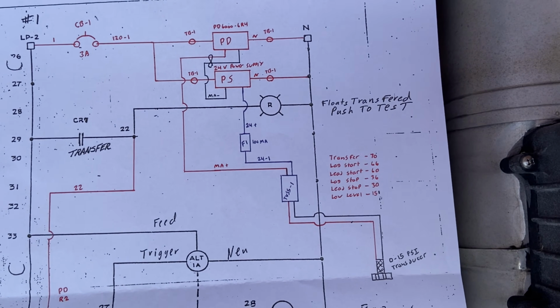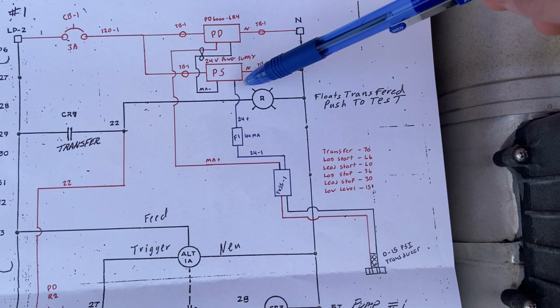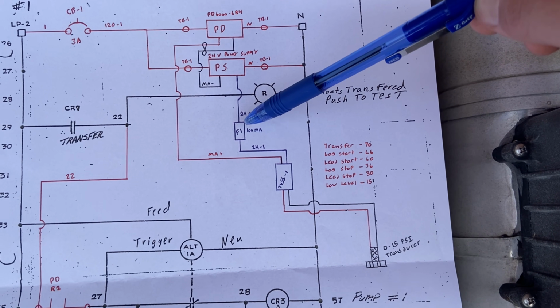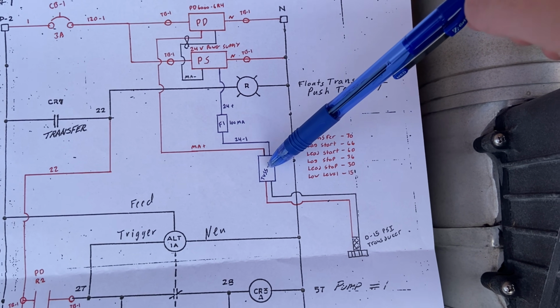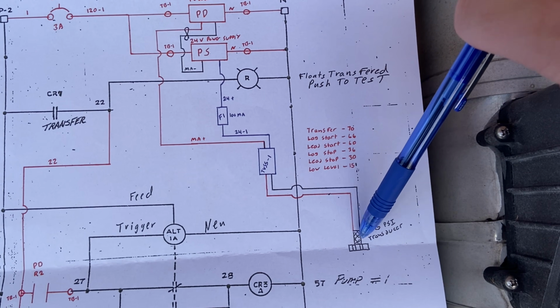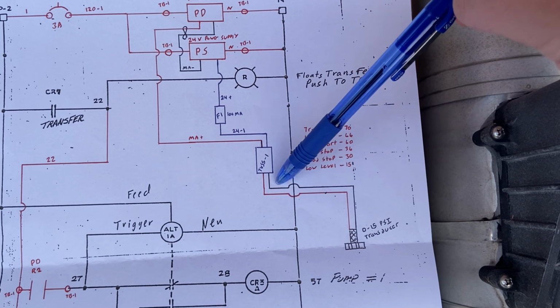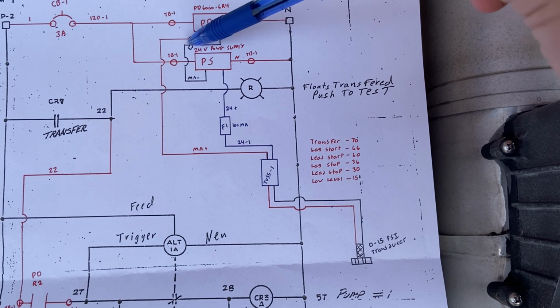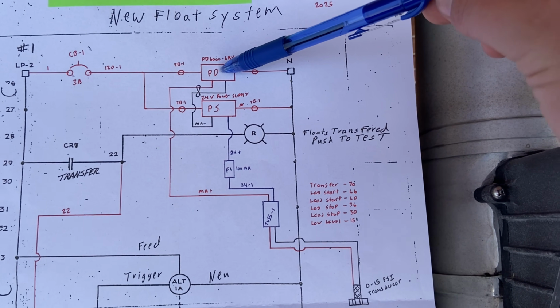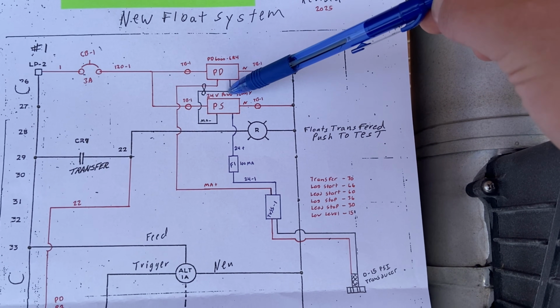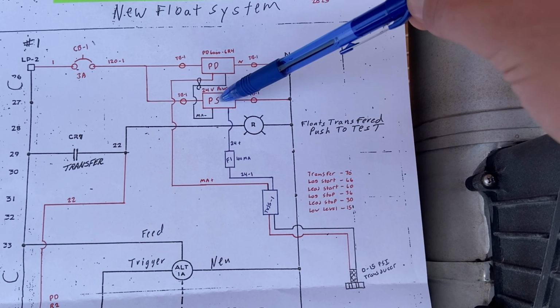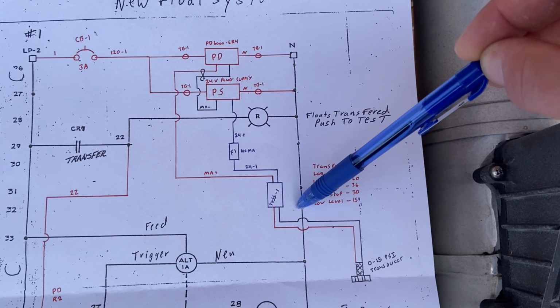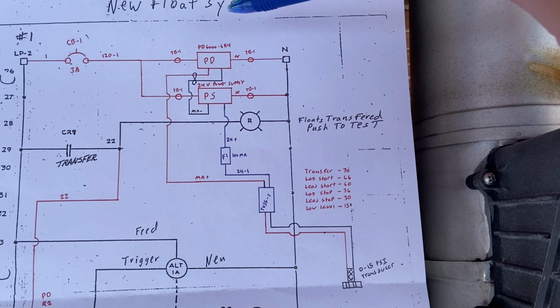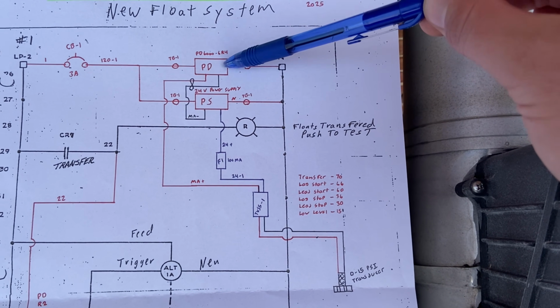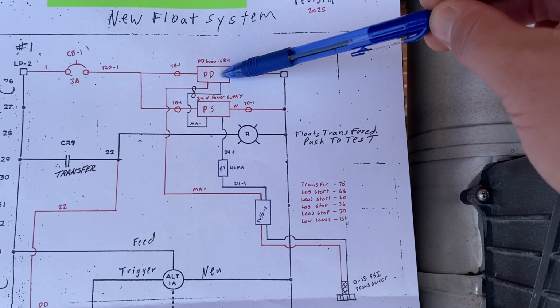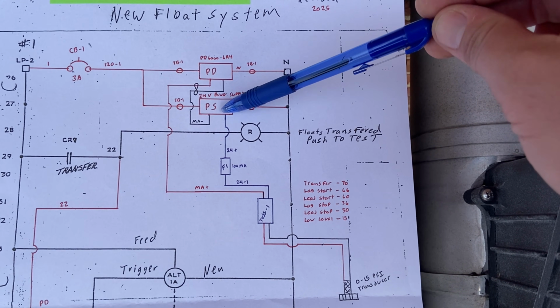Then up here, I drew our milliamp loop, and it of course starts with a 24 volt power supply, goes into a 100 milliamp fuse, into our surge suppressor, out to our transducer in the well, and then back up to our display, and then back down to the power supply as the negative. So I always call it a loop, but it's obviously like any circuit. You have to have your power out and your return, and you have to complete that entire circuit for it to work.